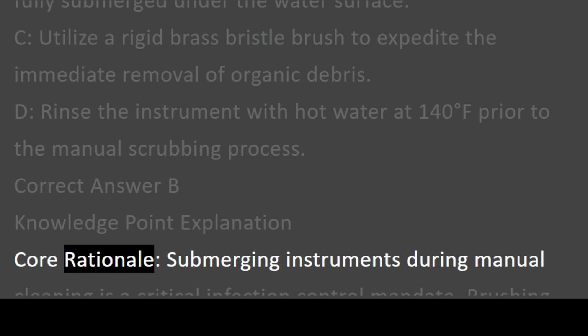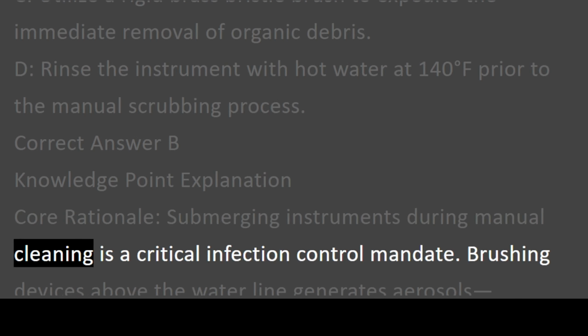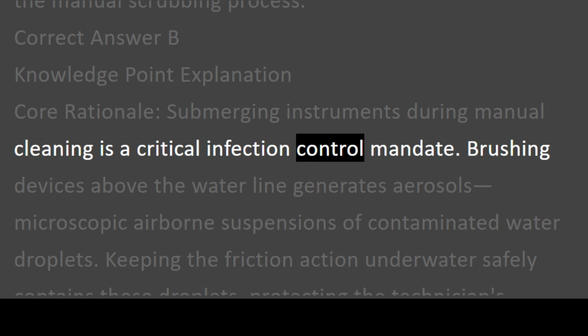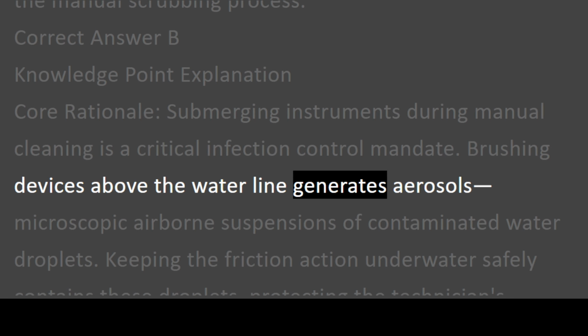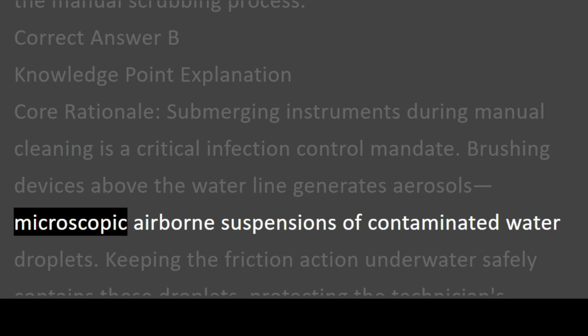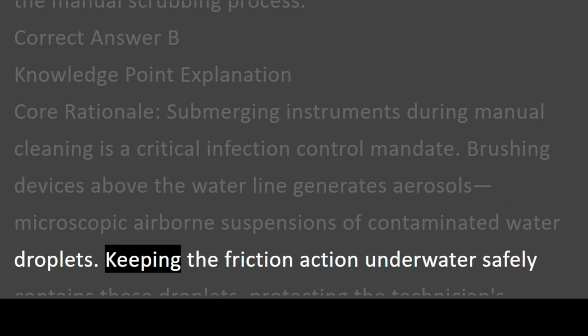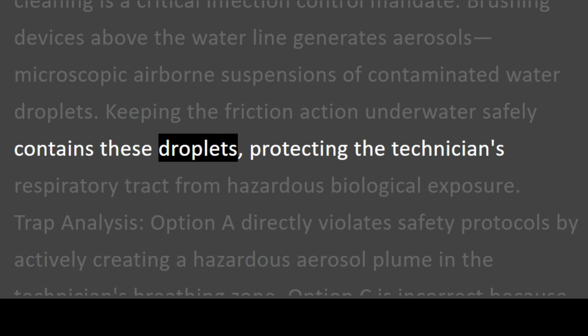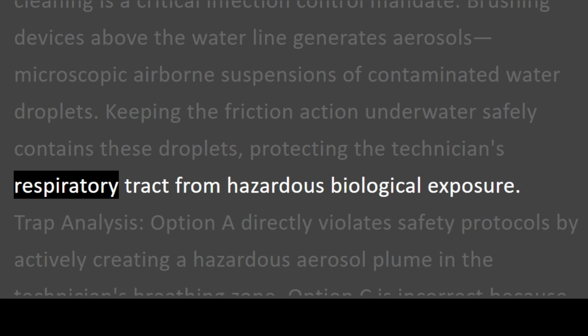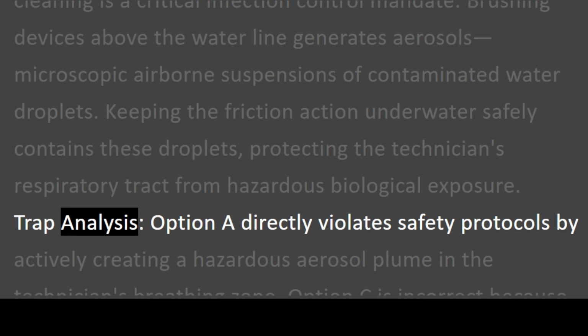Core rationale. Submerging instruments during manual cleaning is a critical infection control mandate. Brushing devices above the waterline generates aerosols, microscopic airborne suspensions of contaminated water droplets. Keeping the friction action underwater safely contains these droplets, protecting the technician's respiratory tract from hazardous biological exposure. Trap analysis.